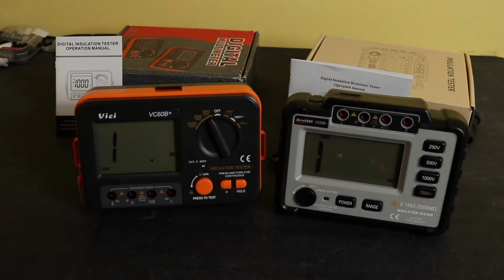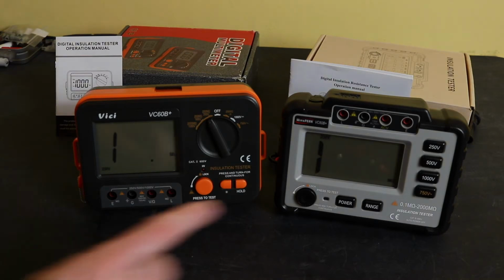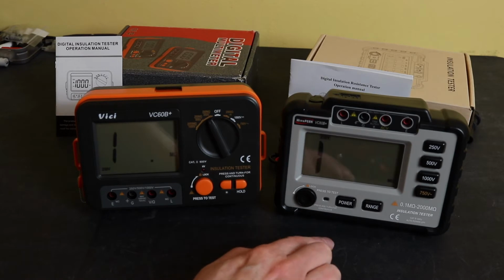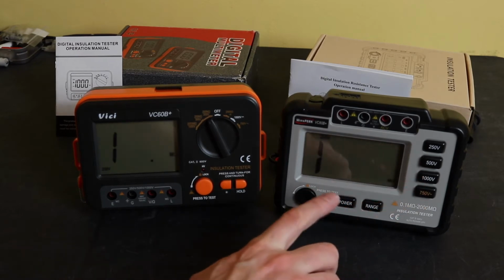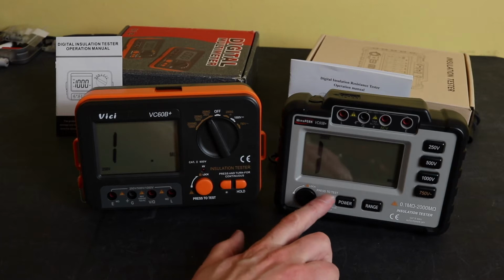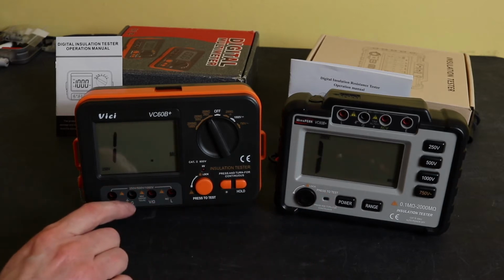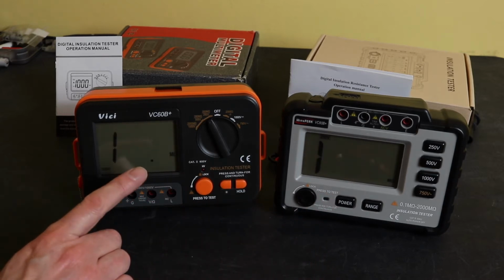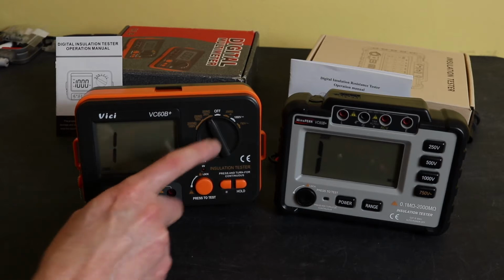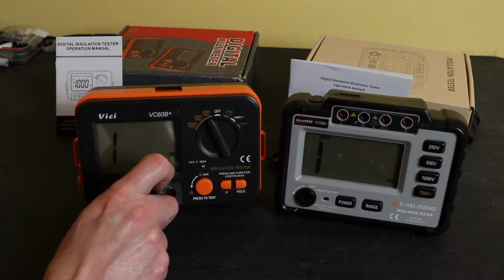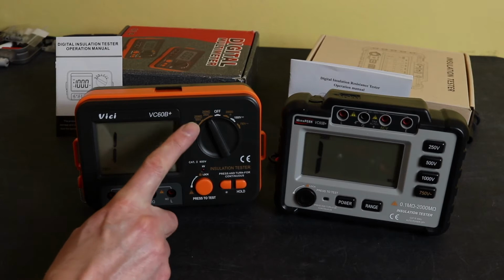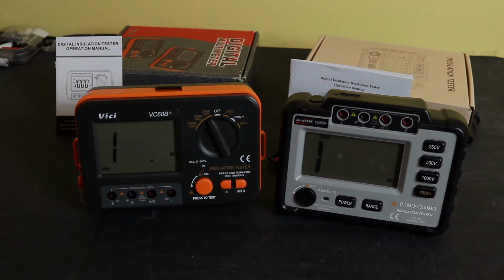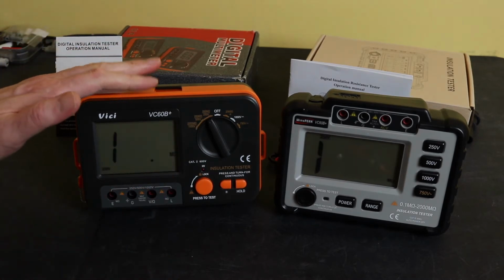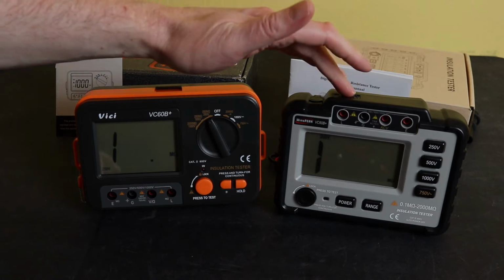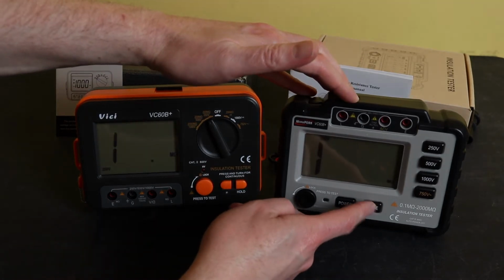With regard to the 250 volt test function, this is where there's another difference between the two units. All three ranges will go up to 2 giga ohms. The 250, 500 and 1000 volt will go up to 2 giga ohms on the WinsPEAK unit. On the Vici unit, it's only the 1000 volt test function that will go up to 2 giga ohms. You can see here only 200 mega ohms on the 500 volt and the 250 volt function. Range selection on this is fully automatic. Range selection on the WinsPEAK is via this button here.